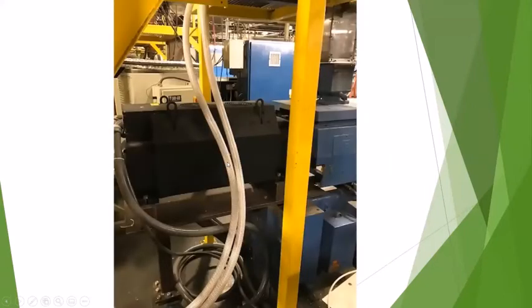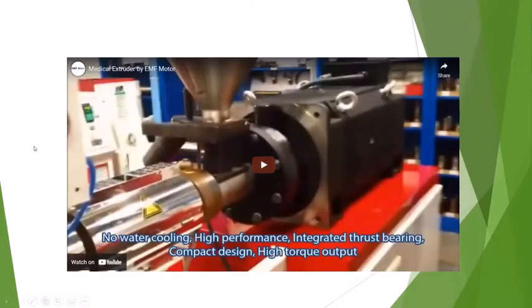And because it's very high pole, you can get up to 66 to 120 poles inside that motor. The torque is extremely high. And then it feeds directly to the barrel and you eliminate the gearing. The efficiency change was dramatic on this application. They were running some PVC. We took the power draw from almost 45 kilowatts down to, I think it was 21, when we were running at the same speed because we had no losses.